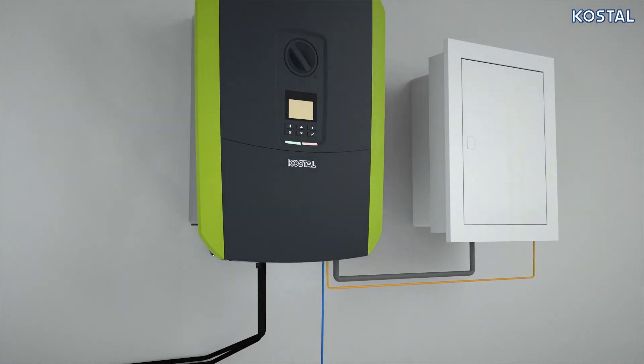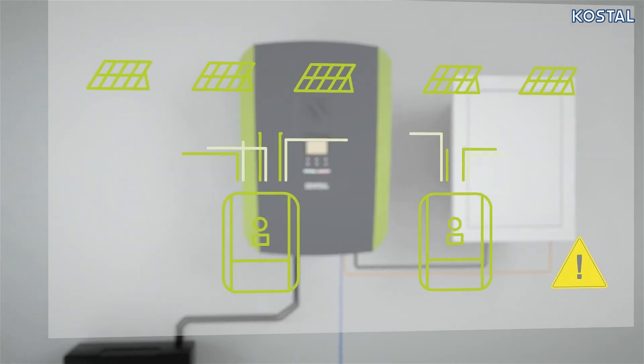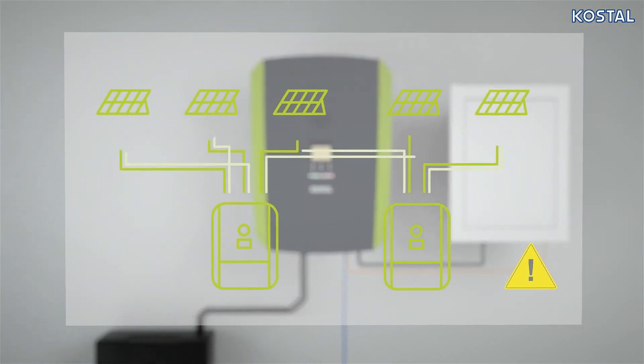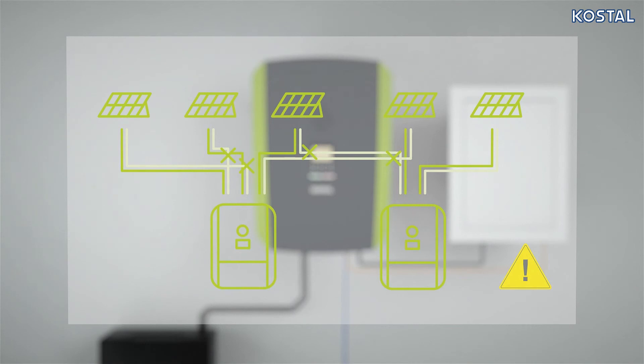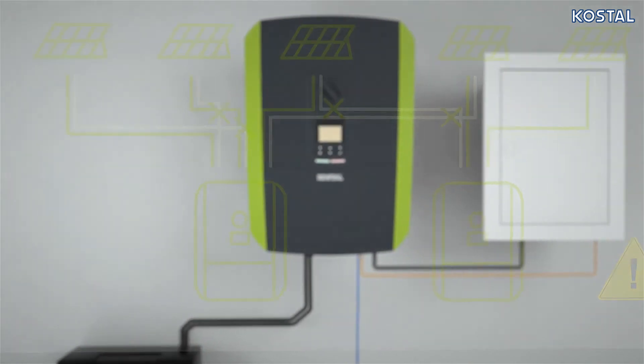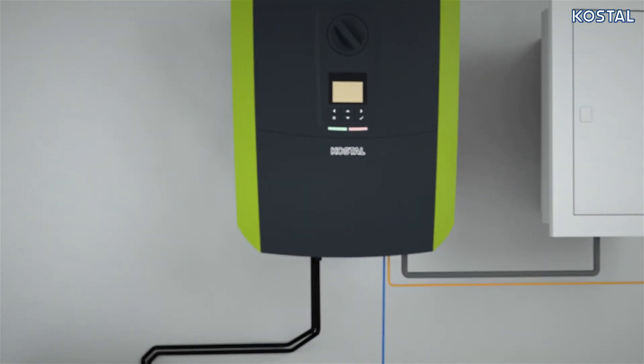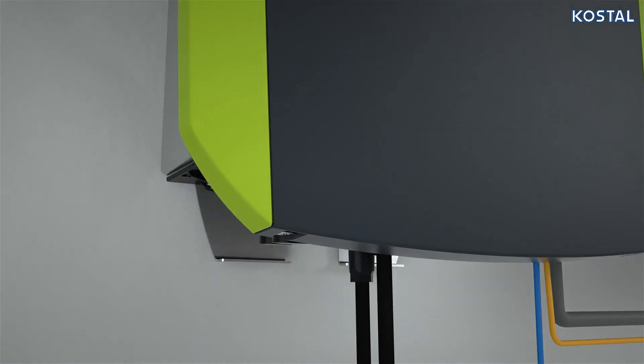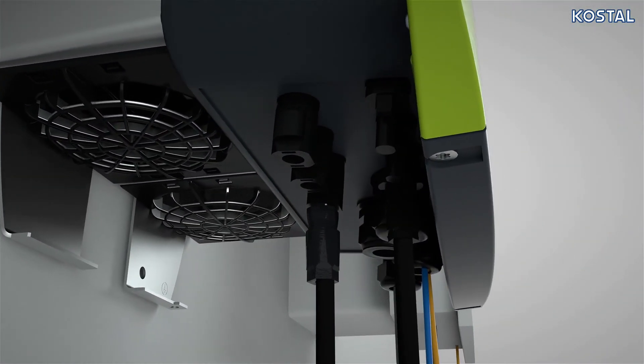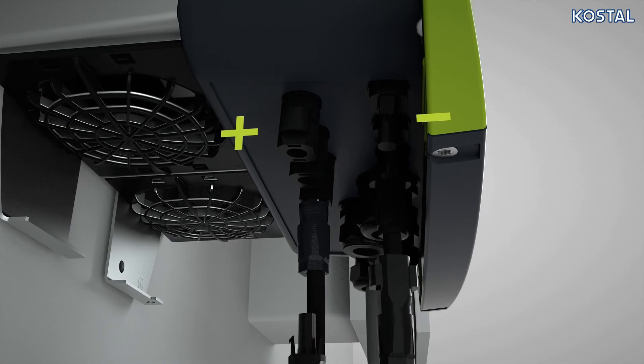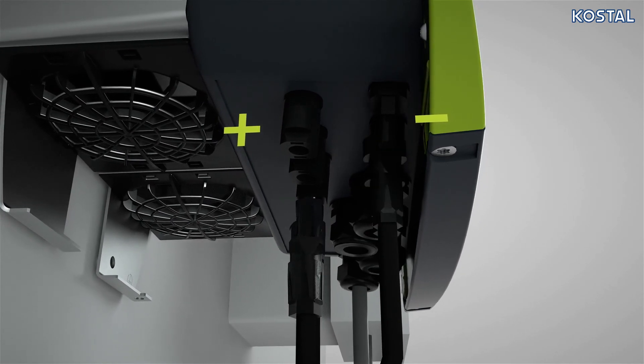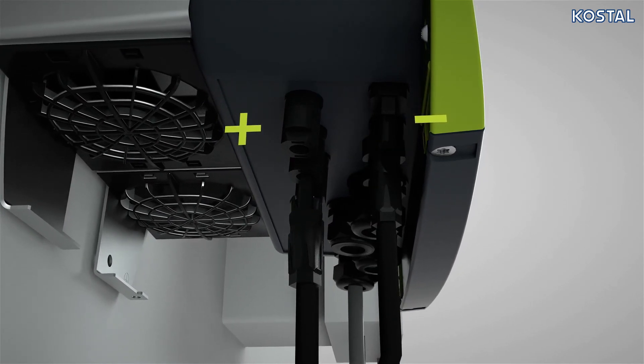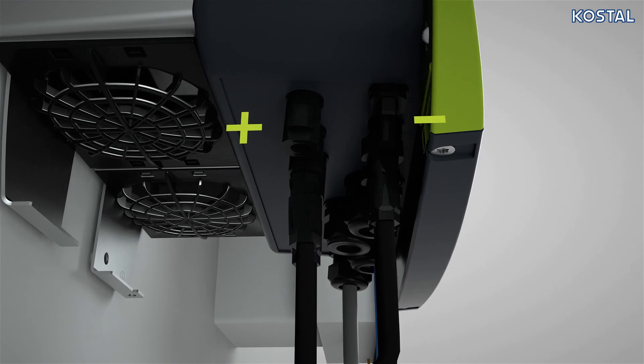Now connect the PV cables with the inverter. Note, if there is more than one inverter in a PV system, ensure that no cross connections occur when the PV generators are connected. Remove the plug seal on the left underside and connect sockets and plugs to DC inputs. Note, ensure correct polarity. The poles of the PV strings must not be earthed.